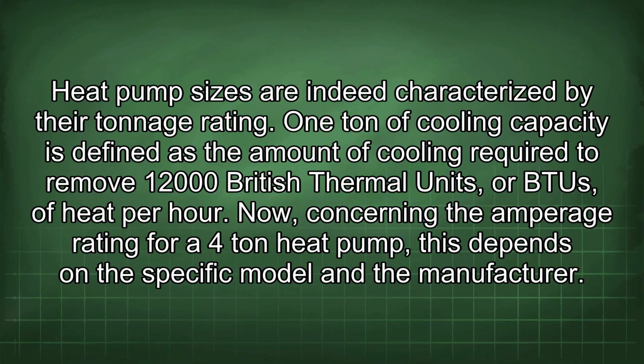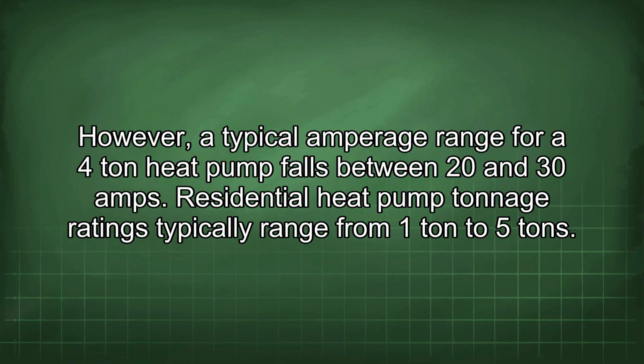Heat pump sizes are indeed characterized by their tonnage rating. 1 ton of cooling capacity is defined as the amount of cooling required to remove 12,000 British thermal units, or BTUs, of heat per hour. Now, concerning the amperage rating for a 4-ton heat pump, this depends on the specific model and the manufacturer. However, a typical amperage range for a 4-ton heat pump falls between 20 and 30 amps. Residential heat pump tonnage ratings typically range from 1 ton to 5 tons.